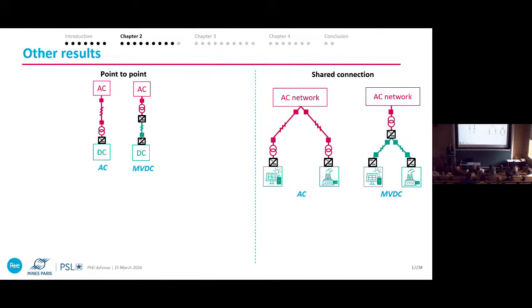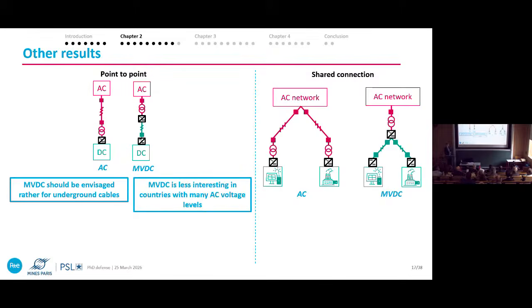Other results from all the sensitivity analysis use cases, divided into point-to-point and shared connection results: first, MVDC should be envisaged rather for underground cables, because underground cables are more expensive overall, and MVDC saves more cost there. Second, MVDC is less interesting in countries with many AC voltage levels. As I said, in this use case I'm obliged to install 63 kV AC, but if you have other AC voltage options, the gap between MVDC and AC becomes thinner. MVDC solves AC voltage gaps, but if you have more options, maybe that has to be investigated.